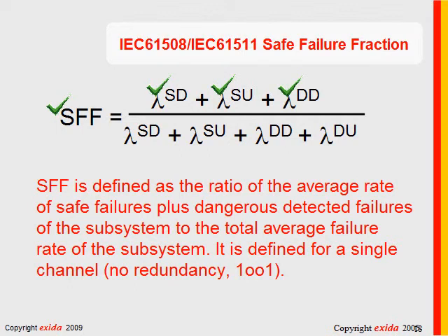All right, let's keep going. A high number is good, 100% is good. A low number, like less than 60%, is not so good. This is a metric that is independent of total failure rate because it's a ratio of failure rates. And it was developed primarily in the context of complicated microcomputer-based safety devices.